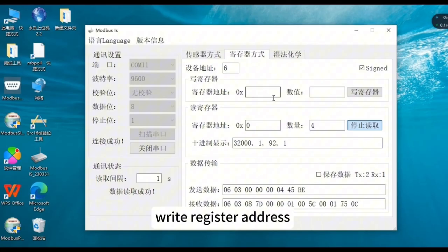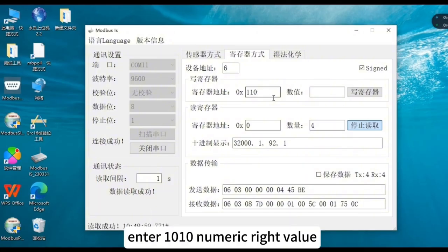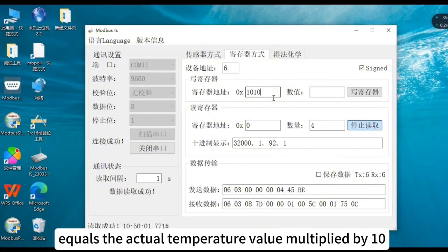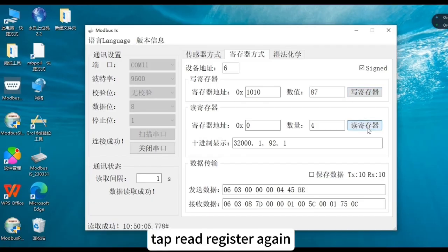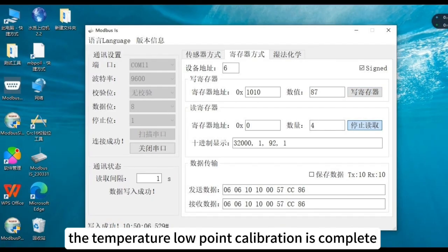Write Register Address. Enter 1010. Numeric write value equals the actual temperature value multiplied by 10. Tap Write Register. Tap Read Register again. The temperature low point calibration is complete.